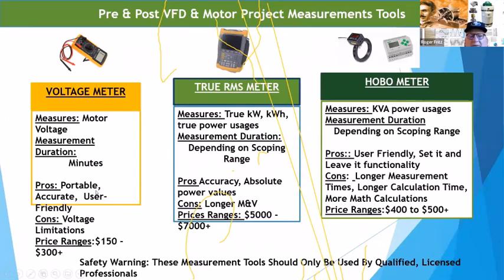The tools that are out there: you've got your standard voltage metering. This doesn't measure any of the harmonics or detail. You've got to go to what they call true RMS metering to actually see all the spiking. And I found this one to be the easiest to use in the market that I've found. These are in a price range of 150 to 300 US dollars for a standard voltage meter that can also have current clamps on it if you want to measure the current. These run anywhere from 5,000 to 7,000. Actually, those are kind of older numbers, they have increased in price some, but it does give you that scoping look at all the details, and understanding what that tool can do can save you thousands and thousands of dollars in operating cost and reliability.